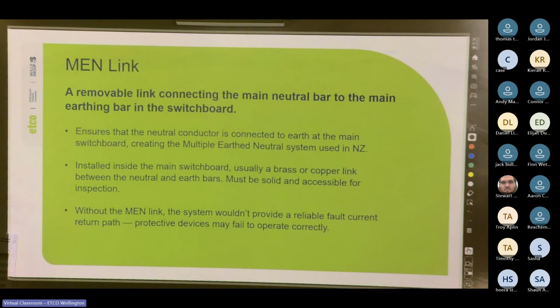Cool, it's the MEN link. It's the heart of our earthing system. It's what it's all based off, ever since 1929. It's what actually ties the neutral to the earth. And if it's loose, missing, or corroded, the whole protective system becomes unreliable. It's not that the protective system won't work, but it becomes unreliable. So it's installed at the main switchboard. It's usually a brass or copper link. Sometimes if the earth and neutral bars are too far apart, we can use a piece of 6mm to go between the earth bar and the neutral bar, or an equivalent size to the main earthing conductor.